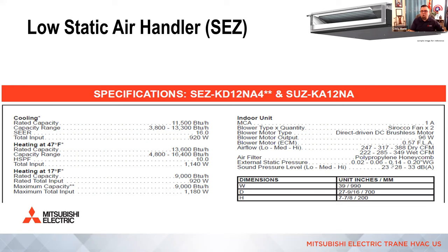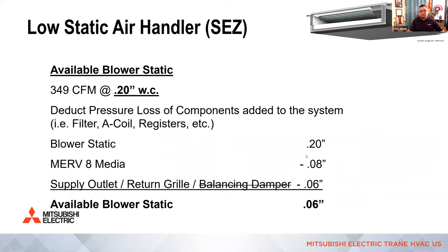All right, so this is a submittal for the SEZ 1-ton system. I'm just going to continue on here to give you an idea of how we come up with available static pressure. So remember, this is the only system we're going to design around: the high static setting, the highest, which is not high static, right? 0.20. So we start with 0.20, but let's say I want to add a nice MERV 8 4 or 5 inch pleated air filter. When I put that larger pleated air filter on that system, we have pressure drop and we have to deduct for that pressure drop. So we started at 349 CFM on high with a wet coil at 0.20, but we deduct 0.08, let's say, for that particular air filter.